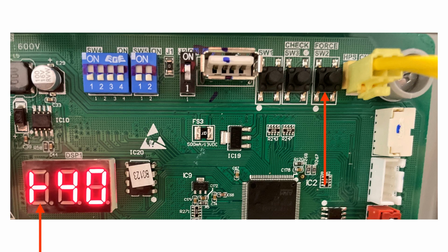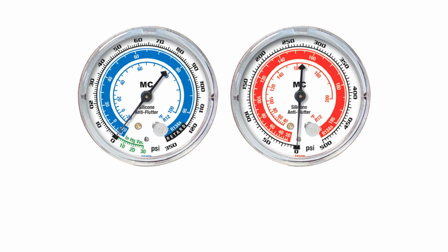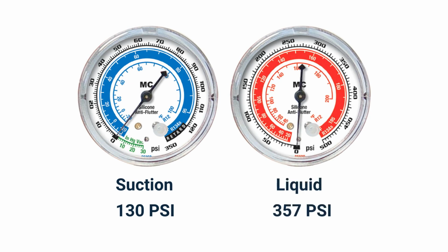Next, you will attach your refrigeration gauges and check for abnormal pressures. In cooling, your suction line reading should be approximately 130 psi. In heating, your liquid line reading should be approximately 357 psi. If your readings do not correlate, you will have to locate the source of the refrigerant blockage. For more information, please visit our other troubleshooting videos on diagnosing the refrigeration circuit.